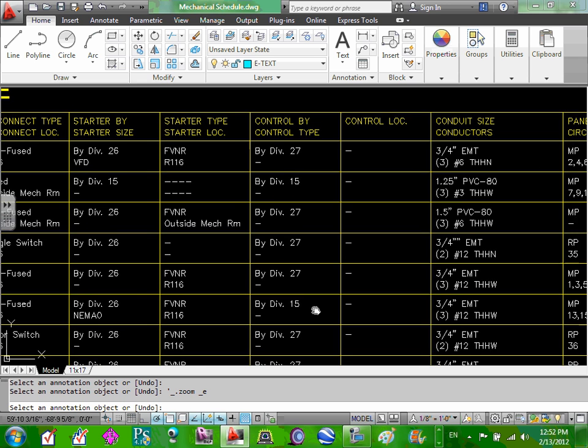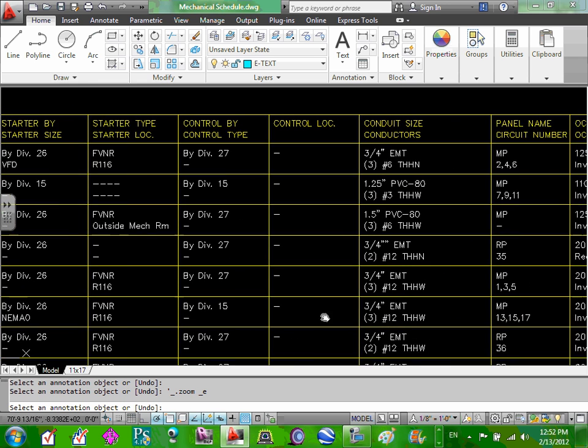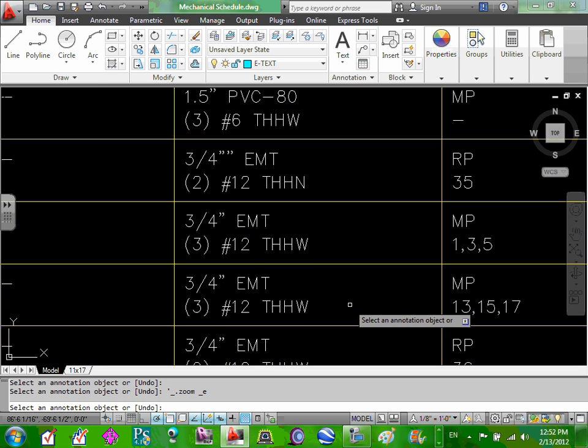Control type, Johnson, whatever. Leave this empty. Size the conductors. 3/4 inch EMT, number 3 is more than enough. You don't want to pull any conductor smaller than number 12. So if your conductor is smaller than number 12, you're going to pull 12.